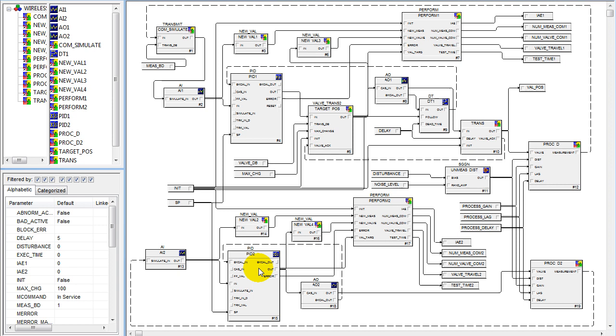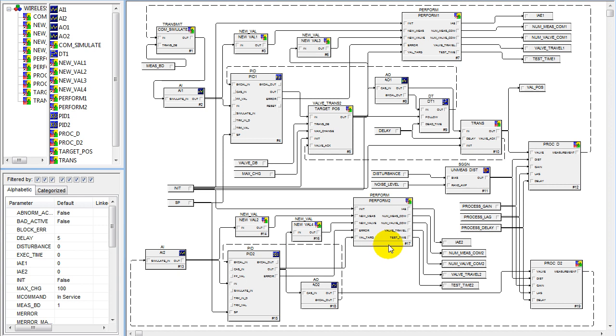The implied valve position that we're calculating is then used as the external reset for the PID Plus. The regular PID has a wired input and wired output. We have simulated two flow processes that are exactly the same so we can compare wired to wireless — the gain, dead time, and time constant are exactly the same for both processes. The performance of each control, wireless and wired, are measured with the performance block.